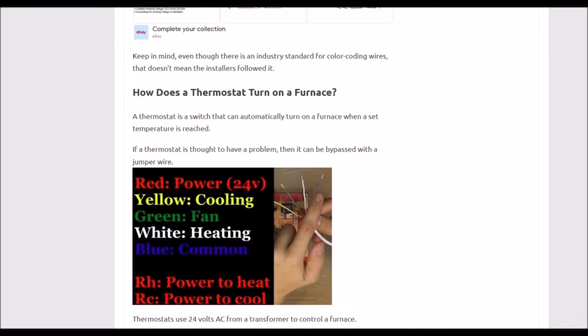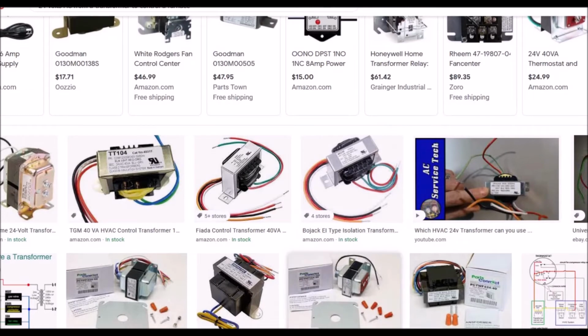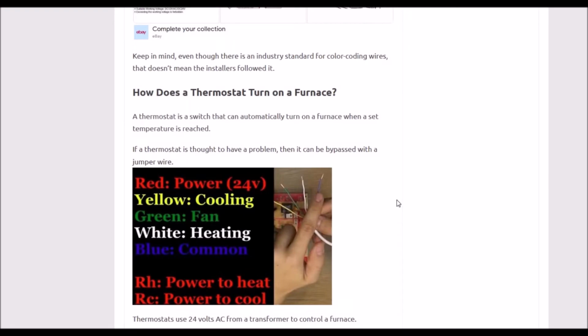Basically, the furnace turns on when it gets 24 volts. The thermostat is powered by a 24 volt AC transformer. And here's an example of what they look like. It basically has 120 volts coming in one side, and it'll be outputting 24 volts AC, which gets fed into the thermostat. When the right temperature is hit on the thermostat, then it'll send out a signal to the furnace to turn on by sending it 24 volts AC.